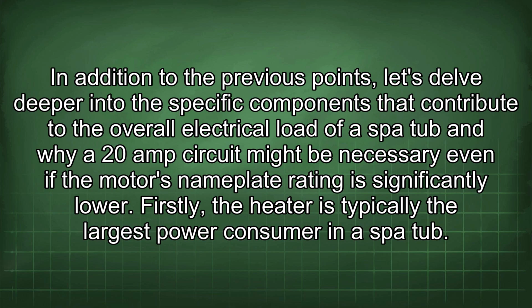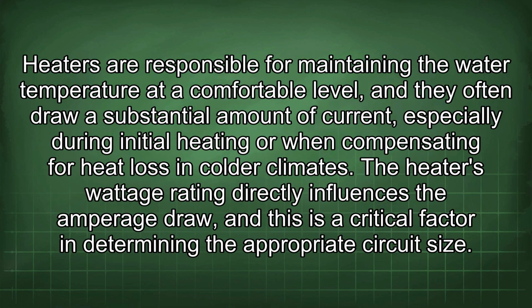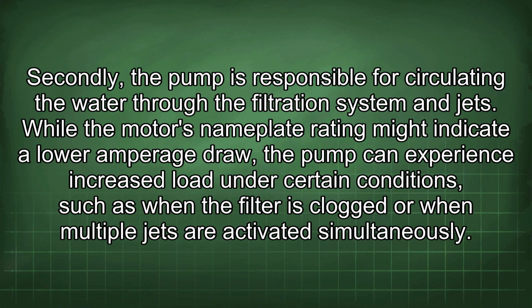In addition to the previous points, let's delve deeper into the specific components that contribute to the overall electrical load of a spa tub and why a 20 amp circuit might be necessary even if the motor's nameplate rating is significantly lower. Firstly, a heater is typically the largest power consumer in a spa tub. Heaters are responsible for maintaining the water temperature at a comfortable level, and they often draw a substantial amount of current, especially during initial heating or when compensating for heat loss in colder climates. The heater's wattage rating directly influences the amperage draw, and this is a critical factor in determining the appropriate circuit size.